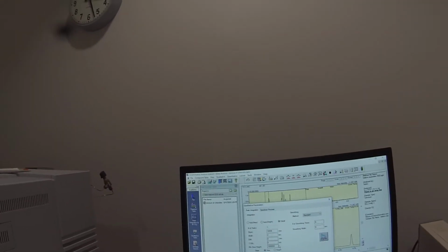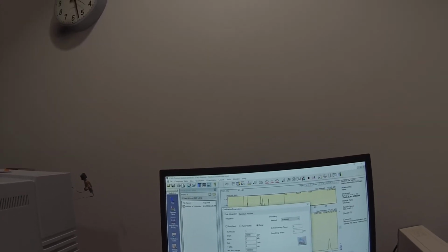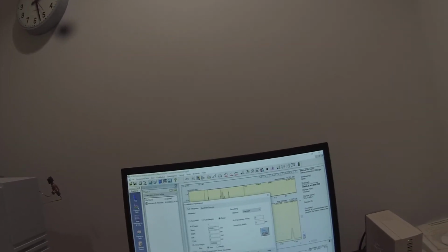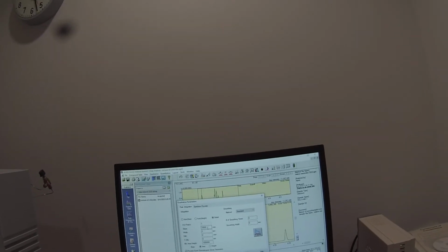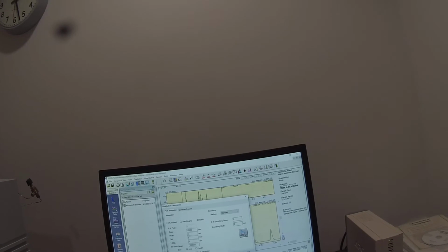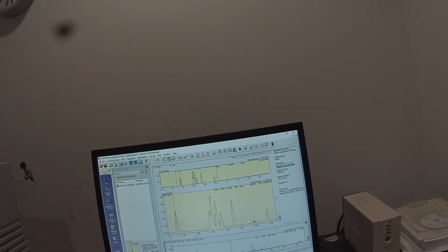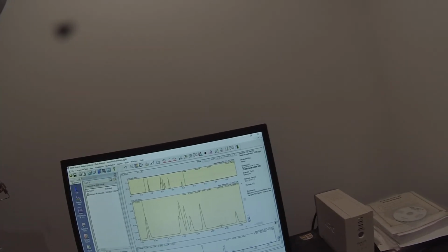So I'm going to go to peak integration for all of the total ion counts. The slope of 10,000 per minute, what that means is that it won't detect a peak unless it's rising at a rate of 10,000 ions per minute. Right? That's to prevent it from accidentally picking up a small baseline blob like this. It never really rises, right?